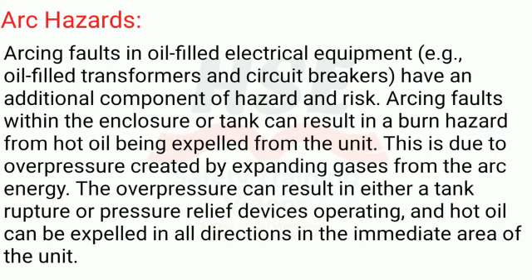Arc hazards. Arcing faults in oil-filled electrical equipment, for example, oil-filled transformers and circuit breakers, have an additional component of hazard and risk. Arcing faults within the enclosure or tank can result in a burn hazard from hot oil being expelled from the unit. This is due to overpressure created by expanding gases from the arc energy. The overpressure can result in either a tank rupture or pressure relief devices operating, and hot oil can be expelled in all directions in the immediate area of the unit.